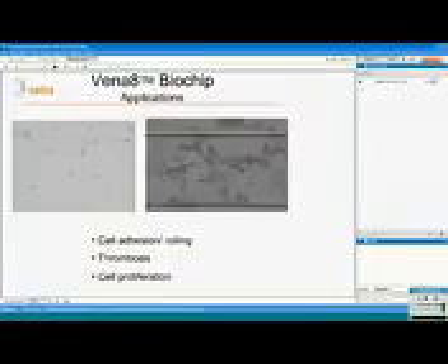The first in line of Cellix's biochips is the Vena 8 biochip. It has 8 microcapillaries, which have a very low volume, 1 microliter per channel. It can be used with bright field and phase contrast microscopy and different magnifications from 20x to 60x and under very high shear stresses, up to 1000 dynes per square centimeter. The applications of this biochip include cell adhesion and rolling under shear stress, thrombosis, and cell proliferation.